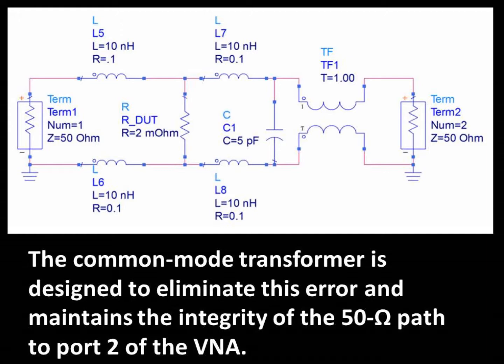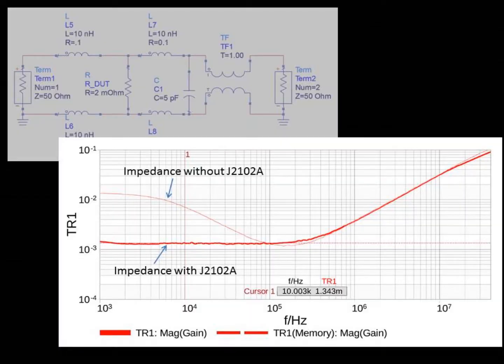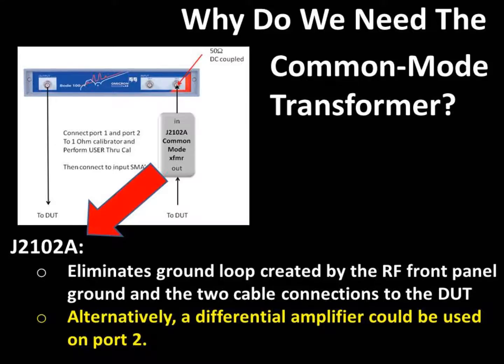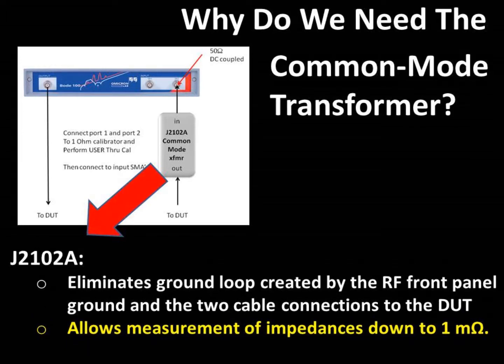The low frequency limitation is generally in the 100 Hz to 1 kHz range. A differential probe could also be used for port 2, but at a loss of sensitivity, degrading the SNR of the measurement and making it more difficult to measure low values. Note that with this common mode transformer, we can easily measure impedance values as low as 1 milli-ohm using this two-port shunt-through impedance measurement technique.